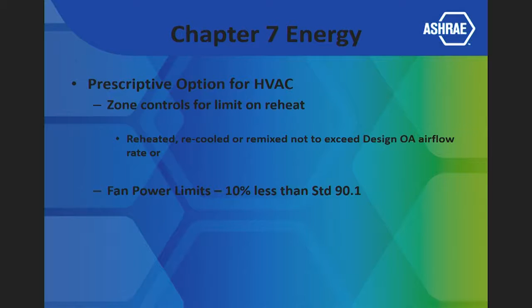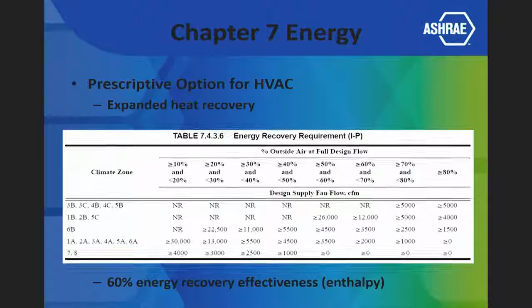Energy recovery. There are new guidelines now about what air handlers in buildings have to do. Mandatory energy recovery at the air handler. Much more stringent. I could have an air handler with a really low percentage of outside air, but it's a big air handler in our climate zone, and now it has to have heat recovery. And it's a type of heat recovery that has a certain efficiency, minimum 60% efficient, which now means I'm into enthalpy heat recovery. Anybody know what the word enthalpy means? It means total energy, sensible and latent. So now you're into what's called heat recovery wheels. A lot more space, a lot more energy, a lot more money up front, first cost.